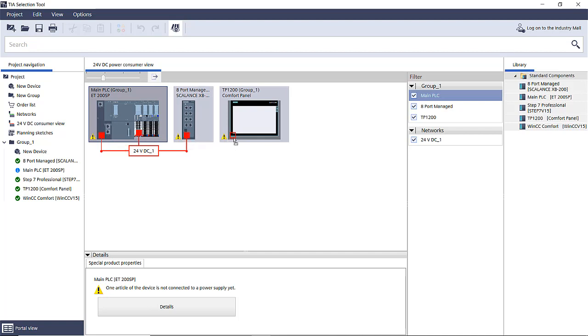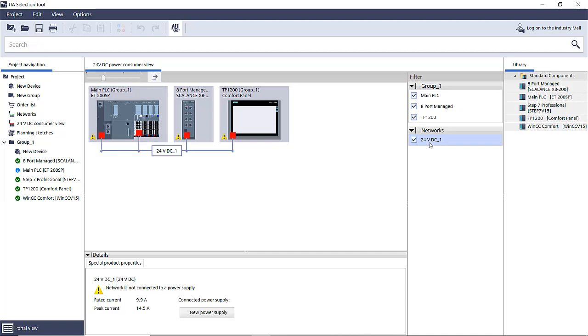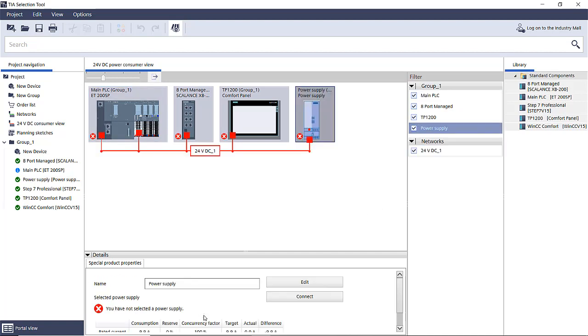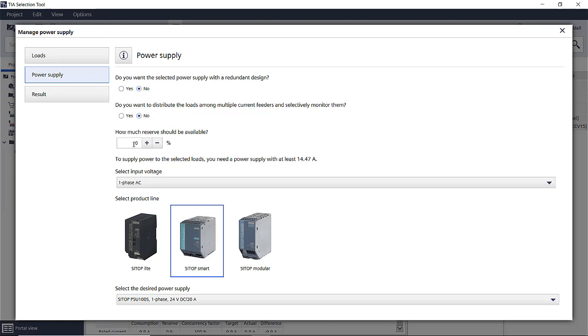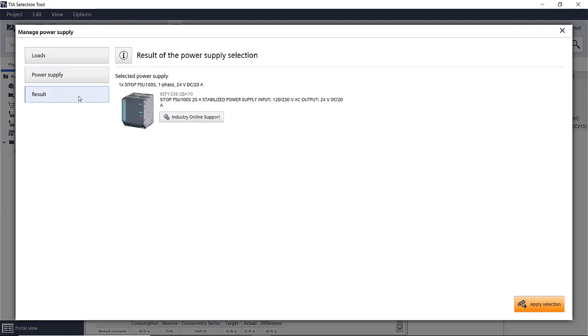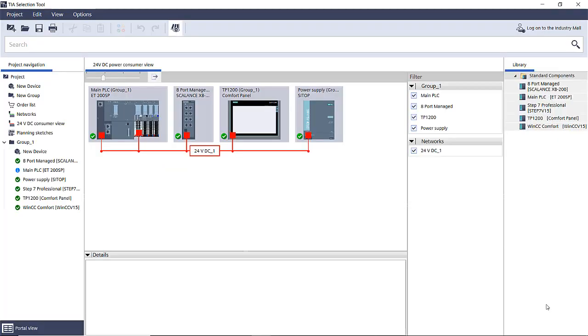So now we'll basically just connect all those power connections between the devices. And after we've done that, we'll click on the 24 volt DC, which will actually allow us to create a power supply. We'll edit it. It will show us the total load requirements. Click on the power supply, we're going to add about 20% reserve just so we have a little extra available. And then we'll hit the result, it comes up with the right power supply, and we apply it. And at this point we have all those hardware components in our bill of material.